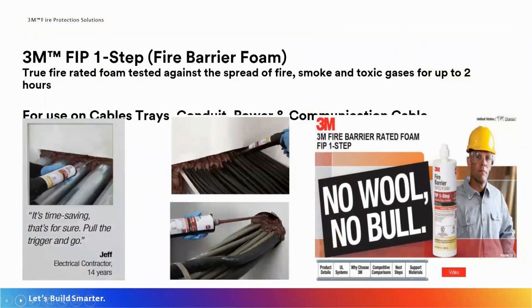One of the things I want to point out about the FIP foam is that this is a true fire-rated foam. It's been tested against the spread of fire, smoke, and toxic gas for up to 2 hours. This is a lot different than the product you would find at your hardware store on the shelf. It isn't like the foam in the can that you would use to seal gaps and cracks around a window or a door. This is a highly specialized foam. It's great for large openings where you have multiple cables penetrating a hole or cable trays. It can be used on conduit as well.